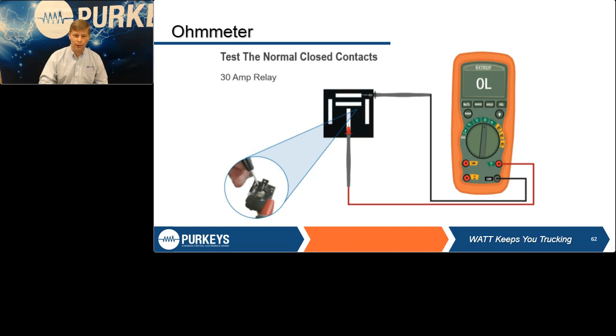Now, a couple other things you can do with a relay: if you energize this relay, you could do the test backwards. Our normally closed contacts would now be open, and our normally open would now be closed. But if you really want to check a relay, you want to test it under load. So you can put it back in service and use our voltmeter like we did before, and we can go across those different contacts and look for voltage drop.